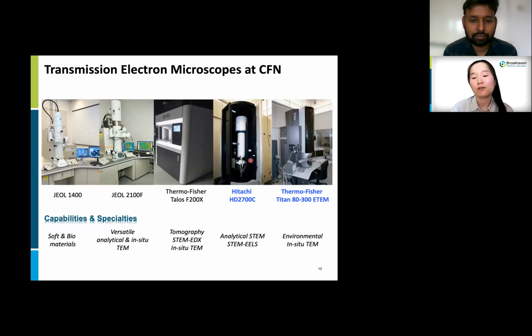Hitachi HD2700C is a dedicated STEM with EDX and EELS, and also it is equipped with a probe Cs corrector, which means that additional optics corrects the errors from electromagnetic lenses. As a result, we can make a much smaller probe beam, so it gives us much better spatial resolution in imaging and chemical analysis.